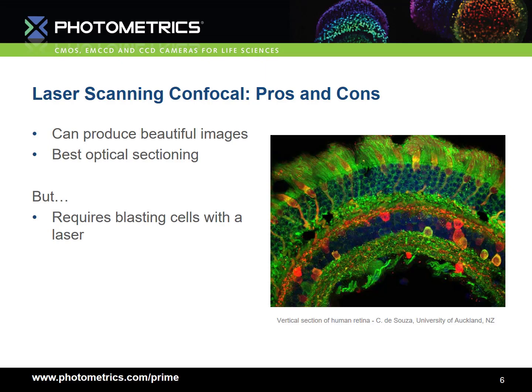But this comes at a cost. Each and every part of our sample must have a laser beam tightly focused onto it, which can be very damaging for live cells, leading to problems with photobleaching and phototoxicity. Also, as we have to scan the entire image, this technique is very slow, with acquisition times of anything from half a second to two seconds per Z slice. Both the high illumination strength and this slow scanning make this technique quite unsuitable for studying live cells. It's also expensive, requiring many precise moving parts and expensive high-powered lasers.